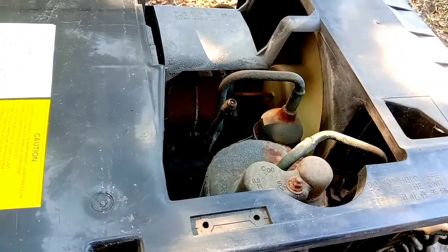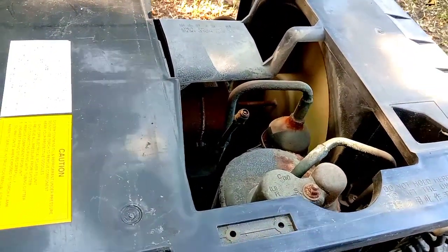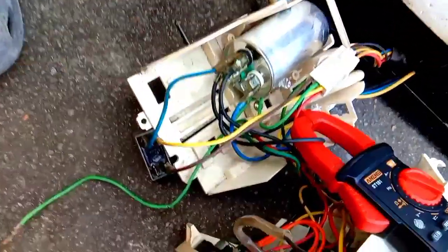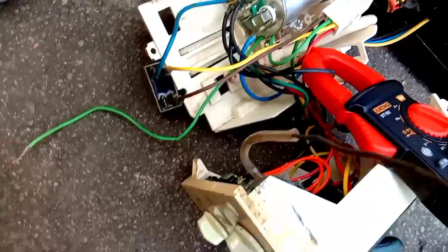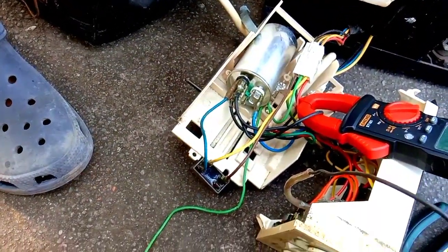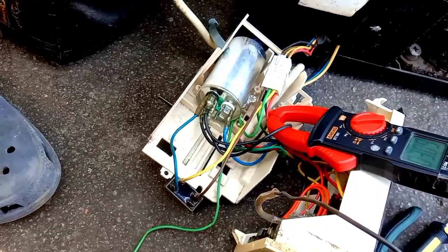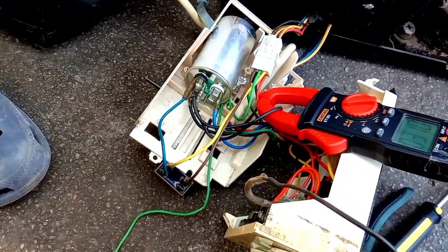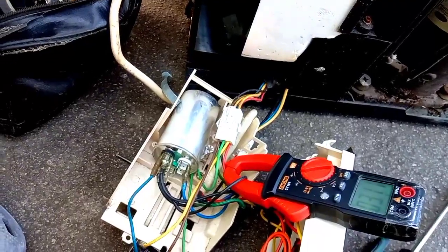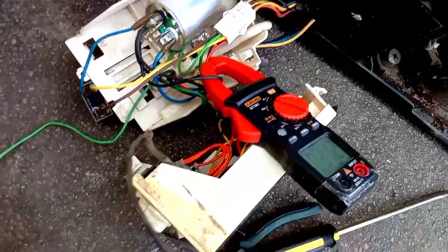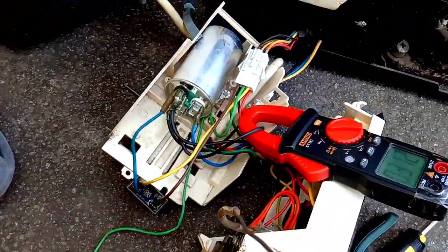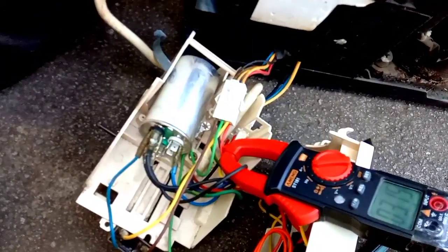So we got 3.02 ampere on the Carrier window type unit. It still functions normally now, and the only defect and problem is the capacitor of the fan motor. So that's it. You see the yellow and brown color of wire and the blue. That's the common wire, blue, from the run capacitor going to the fan capacitor, supplied to the yellow line of the capacitor, which is the neutral line, and the brown line is the line wire from the fan motor.